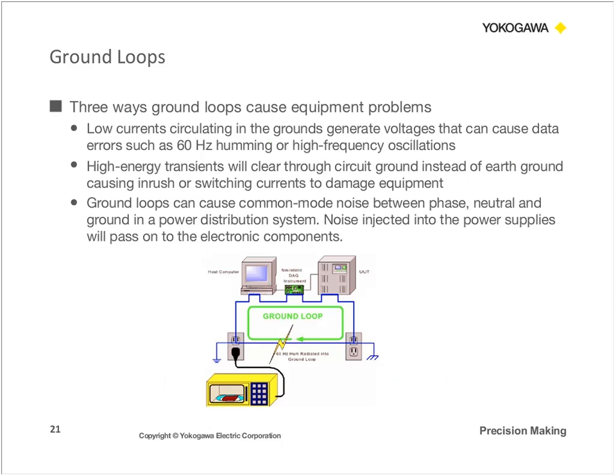So let's take a look at 3 common ways ground loops can cause equipment problems. The very first problem occurs when power measurements are made on data acquisition, and you have low currents circulating through the ground loop. This will generate an oscillating or noise voltage that occurs, as we showed earlier, as a power line 60 hertz humming noise. And if you're dealing with variable frequency drives, it can also occur as high frequency oscillations. So you could really see this as switching noise when you're making the measurements.